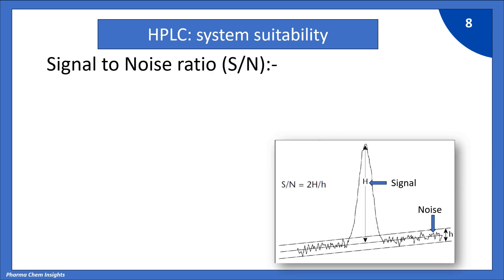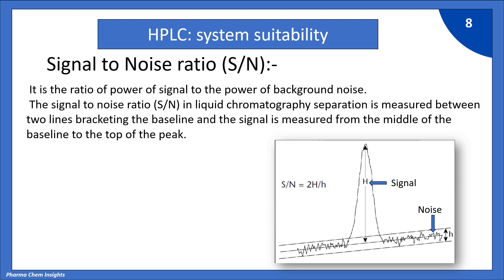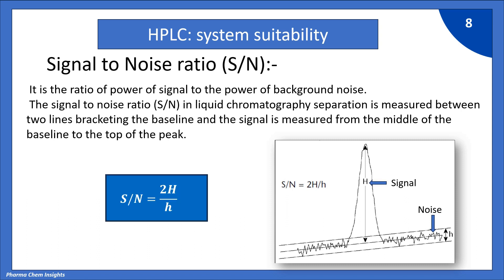Next parameter: signal to noise ratio (S/N). It is the ratio of the power of the signal to the power of background noise. In liquid chromatography, S/N is measured between two lines bracketing the baseline, and the signal is measured from the middle of the baseline to the top of the peak. You can see the figure for that. The formula is: S/N = 2H / h, where H represents the signal and h represents the noise.